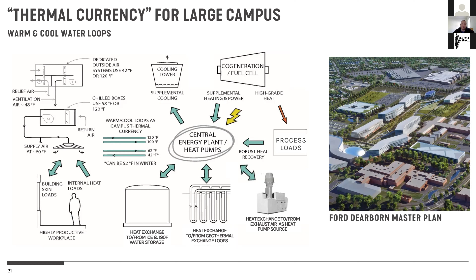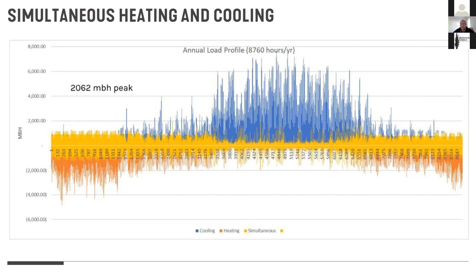When we actually start to take advantage of simultaneous heating and cooling, stealing the heat out of our waste streams—the exhaust streams, the ventilation hoods in chemistry labs—it covers a good chunk of our heating load, to the point where almost all of our heat across the year is simultaneous heating and cooling. Even in cold climates, we can turn it into, from a central plant standpoint, a cooling dominated climate. So I'm less worried about that COP down at 0 degrees because I can find smaller equipment that could pick up that load.